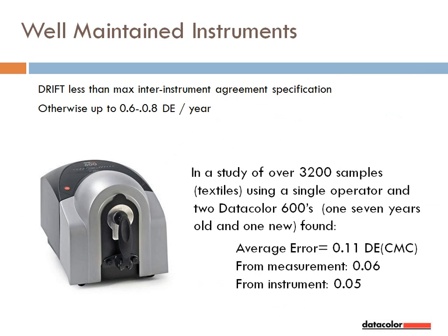A survey of Datacolor service records showed adherence to yearly maintenance recommendations, including reference tile replacements and diagnostics, reduced drifts on the instrument 75 to 80% per year.